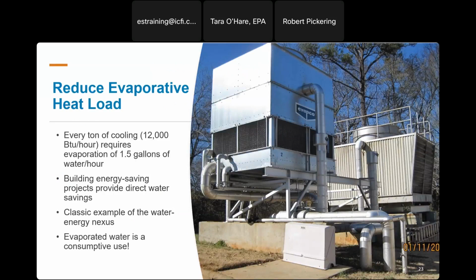Because evaporation is the primary function of a cooling tower and how most of the heat is carried away, this really isn't the focus of our water efficiency efforts. Based on the thermodynamic properties of water, 1.5 gallons of water per hour need to be evaporated for every ton of cooling that is offered. This number is fixed, so you're always going to use 1.5 gallons per hour per ton. Since we want that cooling to occur, we're not trying to limit evaporation at all.